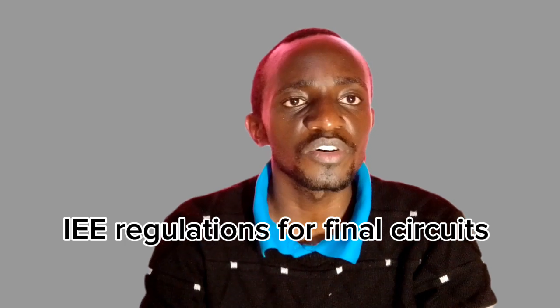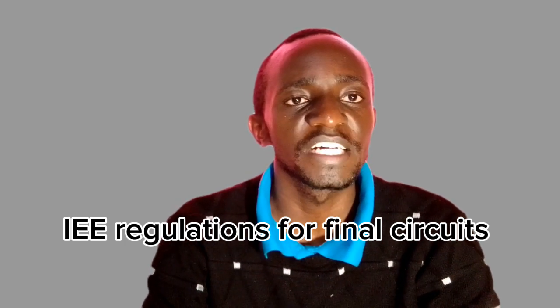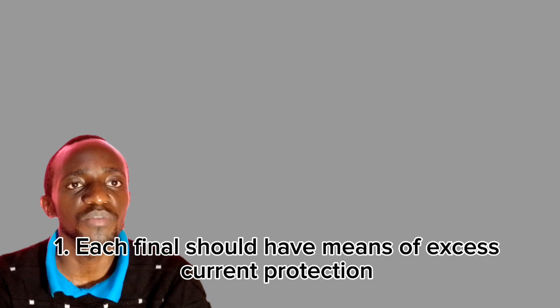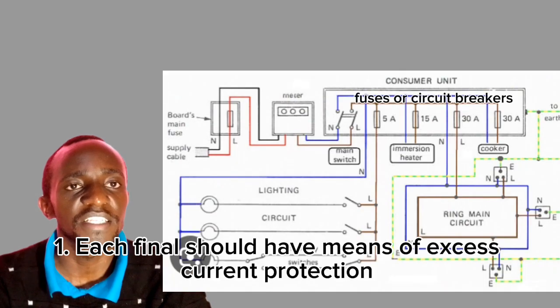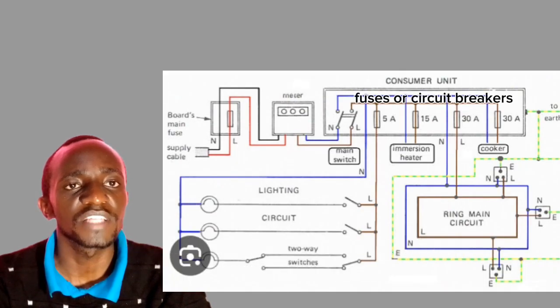So in the previous video, I explained what the IEE is, and I gave you IEE regulations concerning switchgear at the consumer intake point. This institute also has regulations on how final circuits should be dealt with. One of the regulations is that each final circuit in the distribution board should have protection against excess current, and this is where you find that lighting has a circuit breaker which is rated in many cases 5 amperes. The circuit that is controlling the socket outlet also has its own circuit breaker or fuse, which is in many cases rated at 20 amperes.